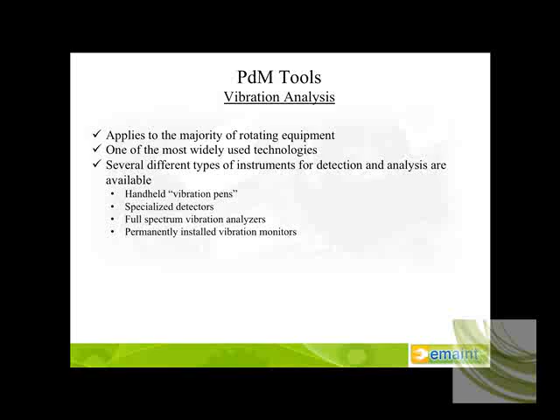So what are they used for? Primarily used to indicate cracks, pits, roughness in bearings. As we mentioned with the full spectrum analyzer, balance or unbalanced issues in rotating equipment, shaft misalignments, bends and cracks, loose parts or loose foot is typically what you'll hear with regard to how that particular rotating train is mounted. Misaligned or damaged teeth gear, deterioration. It will point to some AC and DC motor and controls problems. However, as we go through this, you'll see there's a couple of other tools that, combined with vibration analysis, actually will give you more of an opportunity to even assess what's going on with the motor and the control centers themselves, drive belt problems, and then resonance as well can be detected with vibration tools.